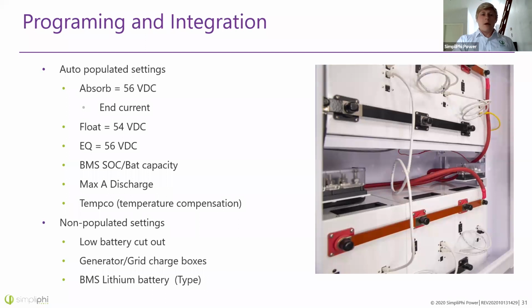So to touch on programming and integration, the AmpliPHI battery is going to auto-populate these set points within the Sol-Ark inverter. It's going to absorb at 56 volts and float at 54. The BMS is also going to communicate to the inverter its current state of charge and its remaining capacity. It's also going to disable temperature compensation through the inverter. So these three settings at the bottom are what you're going to need to program. So ultimately, you're just going to connect the communications, turn on the system, program these three settings, and then you'll be good to go.